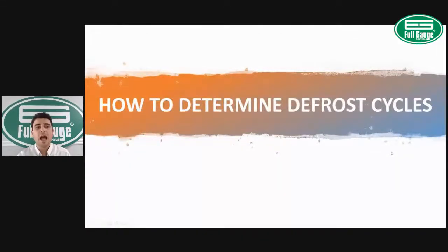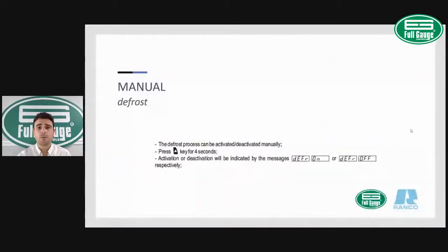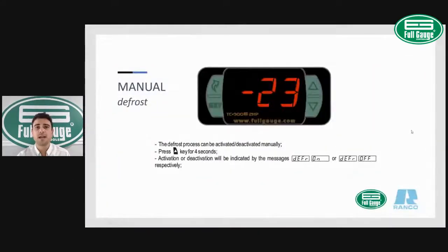How to determine defrost cycles? So the first defrost cycle we're going to be taking a look at is the manual defrost. Manual defrost is a forced defrost. When you adopt digital controllers, most digital controllers will provide you the option of forcing a manual defrost.